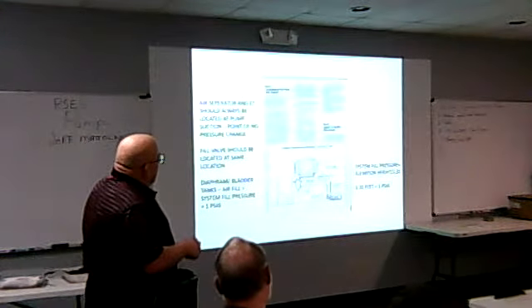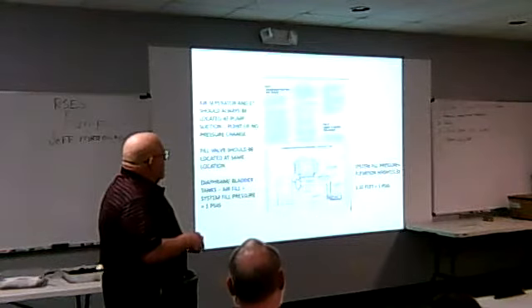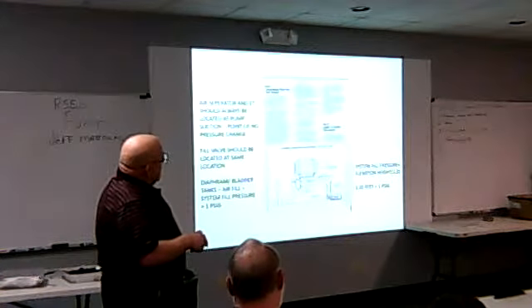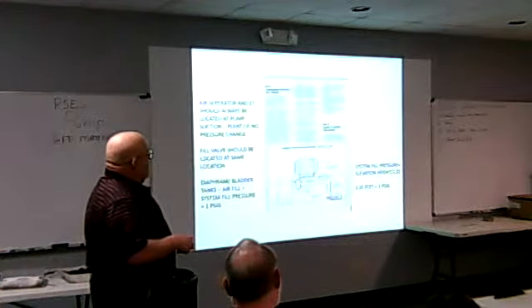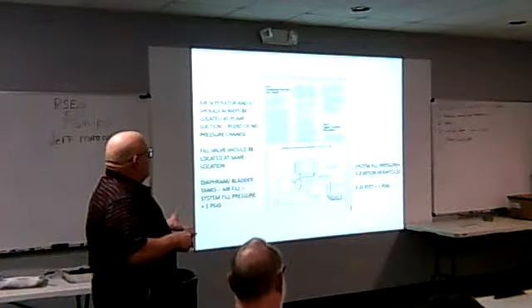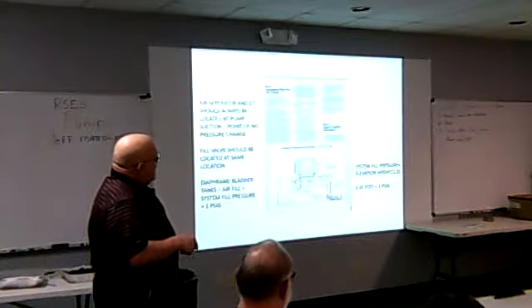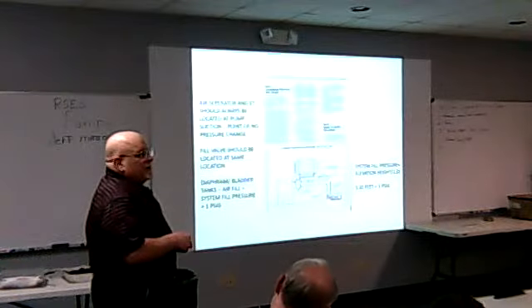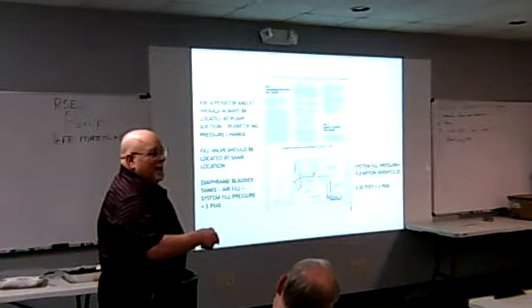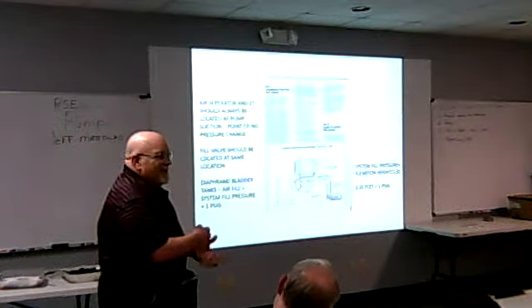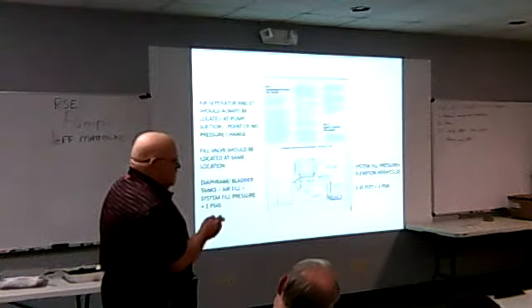So this is called the point of no pressure change. This is where your makeup water is. Because when the pump comes on, if I put my tank over here, okay, I've got 14.7 or 20 pounds of fill pressure here. I charge my tank to 14 over here. Guess what happens when the pump comes on? I've got all this pump head. I just collapsed my tank even more. You always want it at the pump suction.